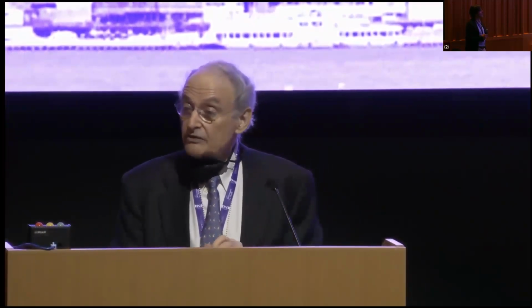And the field inhomogeneities, which are produced by the body itself, become worse at higher field. That scales directly. And so there are a lot of technical challenges at higher fields which have to be overcome. So for practical clinical applications, people often tend to want to stay around 1.5 tesla rather than 3. We do clinical applications on both, but it's often technically a little easier, for a variety of reasons, like trying to do synchronization with EKG, at the lower field.